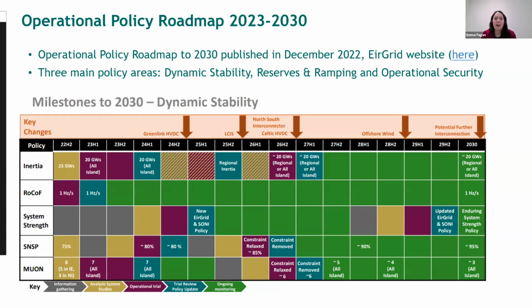At the moment there is a 4,000 megawatt second synchronous condenser in the southwest of Ireland. We're currently procuring additional sites, up to 10,000 megawatt seconds in this round, and it'll depend on where the successful applicants come from. Our current inertia floor is 23,000 megawatt seconds, made up of conventional generation and synchronous condensers as well.